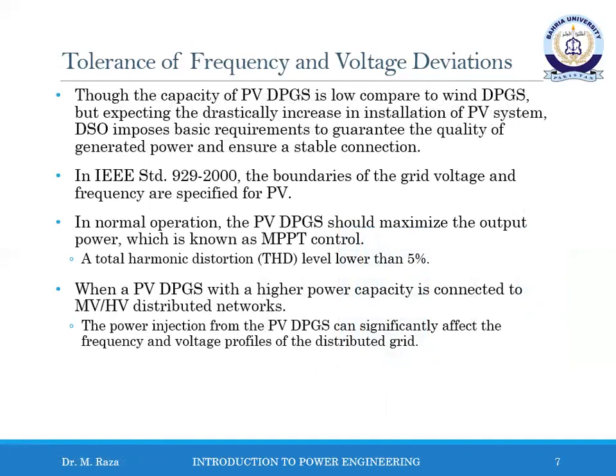The capacity of PV distribution power generation systems is low compared to wind distribution power generation systems, but as PV system installation is expected to increase drastically, the DSO imposes basic requirements to guarantee the quality of generated power and ensure a stable connection while considering the PV system. In IEEE standard 929-2000, the boundaries of the grid voltage and frequency are specified for PV.